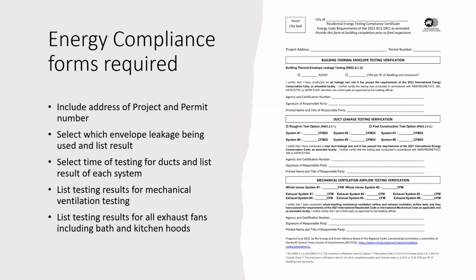That, in my opinion, is the best way to show compliance and to keep it on the same level for all builders. It must include the project and permit number, and show the results of leakage tests, the duct testing for every system, and mechanical ventilation testing. There's also room for bath fan and kitchen exhaust system testing, which is now part of the 2021 IRC, IECC, and mechanical code requirements to have those tested and verified for compliance of ventilation air.